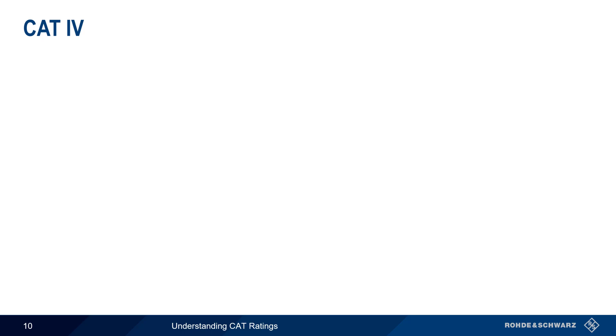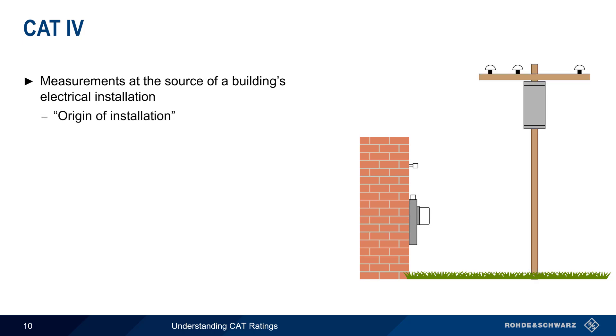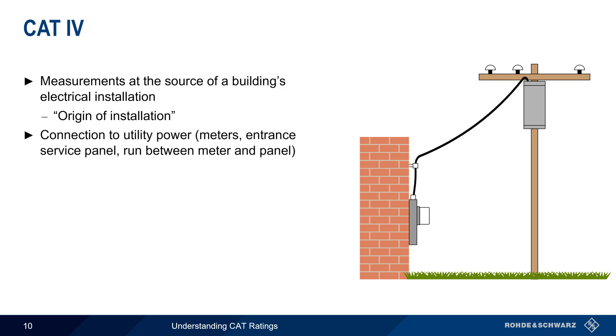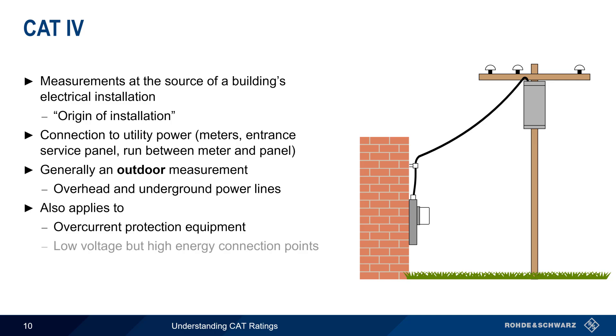The highest category is CAT 4, which applies to measurements made at the source of a building's electrical installation. This is sometimes called the origin of installation, because it involves the connection between the utility power and the meter, the entrance service panel, as well as the run between the meter and the distribution panel. CAT 4 is generally an outdoor measurement, and applies to both overhead and underground power lines. It also applies in some special cases, such as for overcurrent protection equipment, or for connection points that are low voltage but high energy.